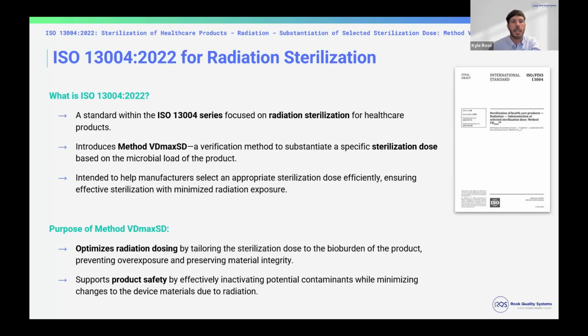The last sterilization standard that is newly acknowledged by the FDA is this ISO 13004. This is for radiation sterilization. So this is a whole series on radiation sterilization for healthcare products. It introduces a specific method for identifying the verification dose and the specific sterilization dose, so the VD max and SD, based on the microbial load of the product. It's intended to help manufacturers select the appropriate sterilization dose, ensuring that you have an efficient sterilization process when you are going through the validation of your sterilization.